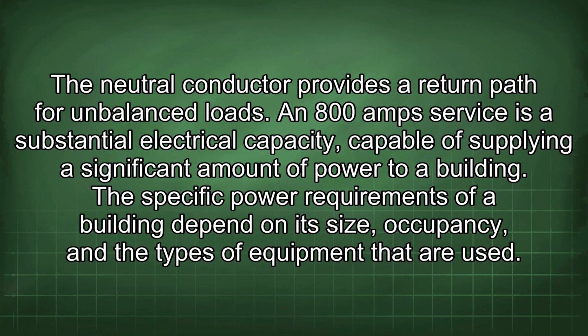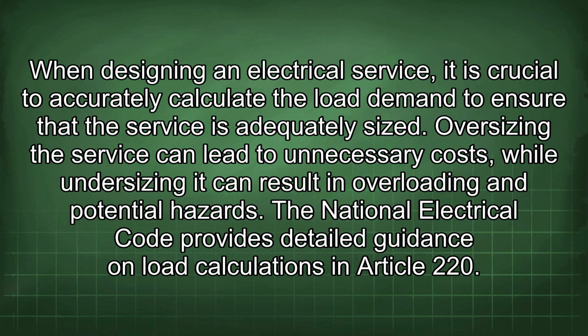An 800 amp service is a substantial electrical capacity capable of supplying a significant amount of power to a building. The specific power requirements of a building depend on its size, occupancy, and the types of equipment that are used. When designing an electrical service, it is crucial to accurately calculate the load demand to ensure that the service is adequately sized. Oversizing the service can lead to unnecessary costs, while undersizing it can result in overloading and potential hazards.